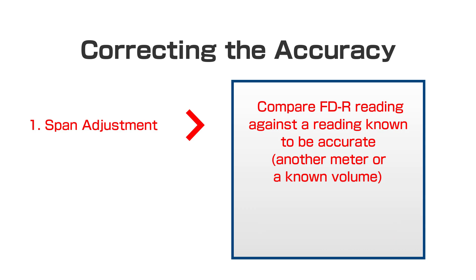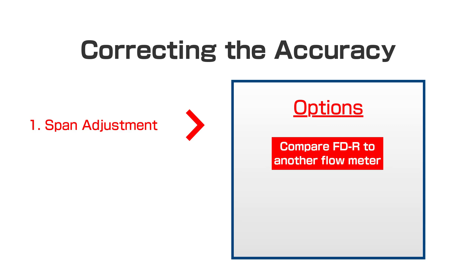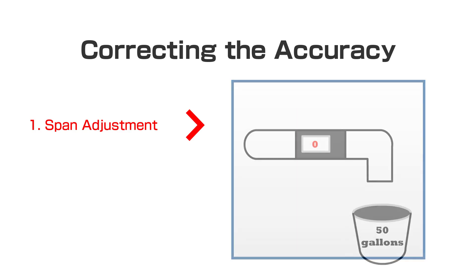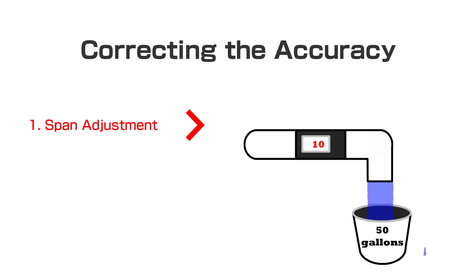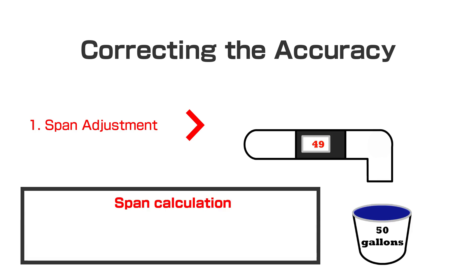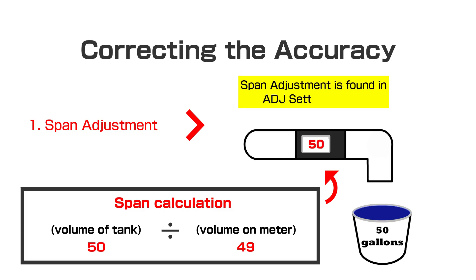Here's an example. If I have an FDR flow meter on a pipe and I want to verify it's reading accurately, I can either compare the flow rate to another flow meter on the same line, or compare the accumulated flow value as I fill up a 50-gallon tank. If I fill up the tank and the FDR only reads that 49 gallons have passed through, I can calculate the required span by dividing the actual amount — 50 gallons — by the FDR's measured amount — 49 gallons — then enter this value into the span adjustment setting to correct the flow rate.